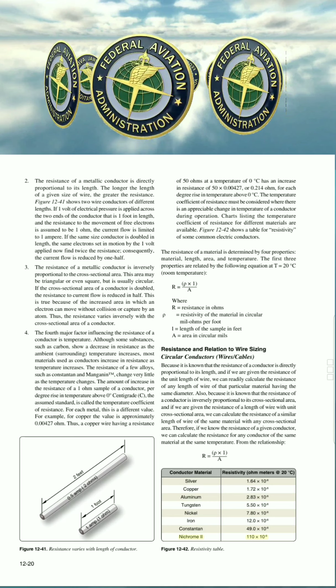From the relationship R equals ρ times L/A, conductor material resistivity, ohm meters at 20 degrees Celsius: silver 1.64 times 10^-8, copper 1.72 times 10^-8, aluminum 2.83 times 10^-8, tungsten 5.50 times 10^-8, nickel 7.80 times 10^-8, iron 12.0 times 10^-8, constantan 49.0 times 10^-8, nichrome 110 times 10^-8. Figure 12-41. Resistance varies with length of conductor. Figure 12-42. Resistivity table.